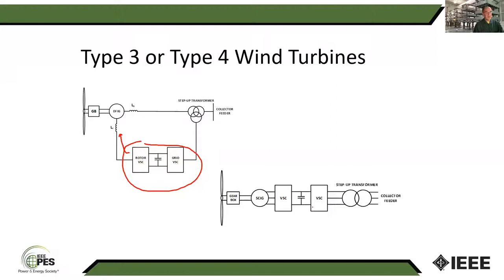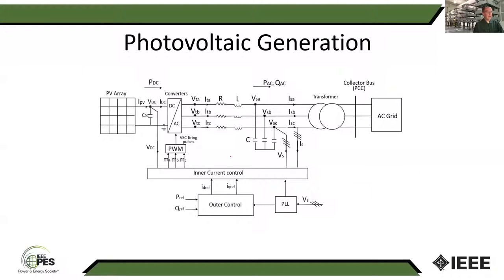The same thing with a type 4 wind turbine. If we get to a photovoltaic converter, we can have a similar thing. But now this DC voltage is going to be controlled to get the most power out of the PV array. So a PV array, PV cells are basically diodes. And so you want to bias that diode, so you can think of a VI characteristic. And so there's going to be some point in this characteristic which is the maximum power point. And so if you bias this by controlling this voltage, you can shift the current that gets out of it to get the maximum power for whatever level of sunlight and whatever the temperature is in the solar cells.